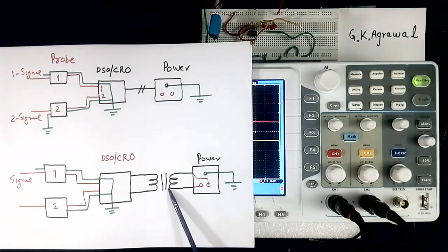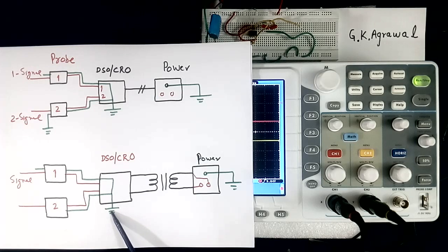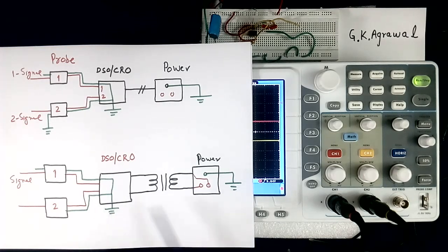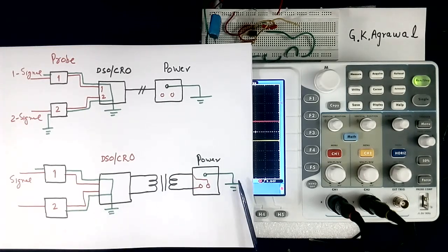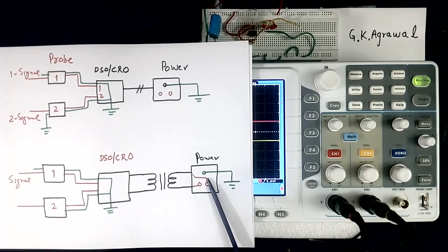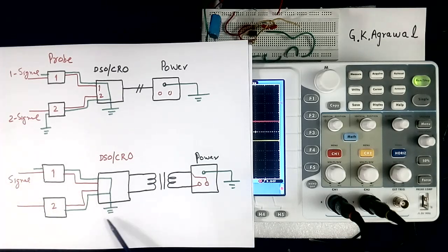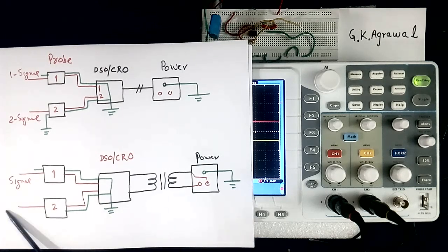Another way of using a CRO is to connect an isolation transformer between the incoming supply and the CRO. This is a 1-to-1 transformer. In this case, the grounding of the AC input signal and the power supply can be different. This is a much safer way of using a CRO. Please connect a transformer between CRO and power. Then this common point can be kept floating and connected to the signal common wherever required.